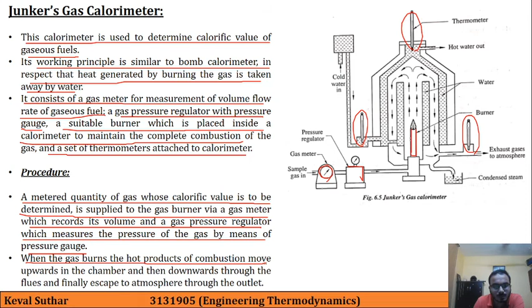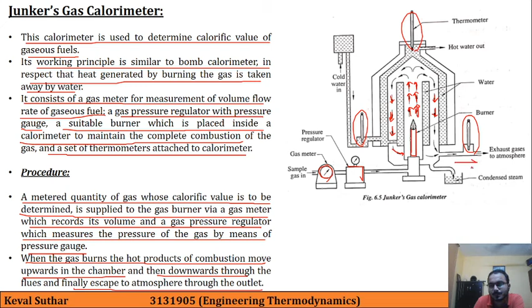Now the procedure: a metered quantity, that is a specific quantity of gas whose calorific value is to be determined, is supplied to the gas burner via the gas meter, which records its volume, and the gas pressure regulator, which measures the pressure of the gas by means of the pressure gauge. Now when the gas burns, a lot of hot products of combustion move upward in the chamber. That is, over here the arrows indicate that the gases will move upward. And then they move downward, as you can see on both sides, and finally escape into the atmosphere through the outlet over here.